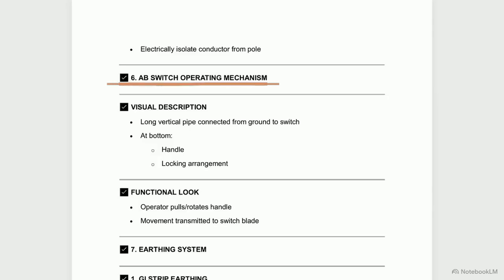This technical breakdown shows the operating mechanism for that exact switch. You'll notice a long vertical pipe connecting the top blades all the way down to a manual handle at ground level, allowing an operator to safely cut the power from below.